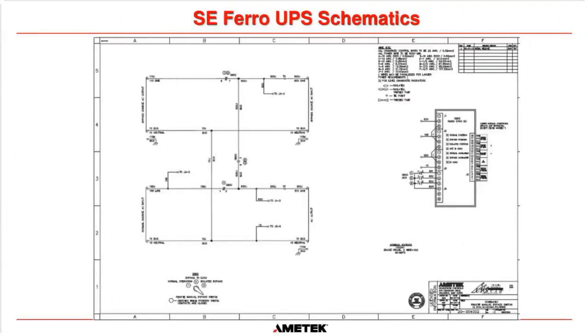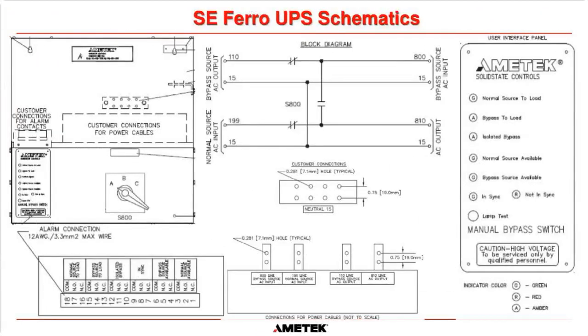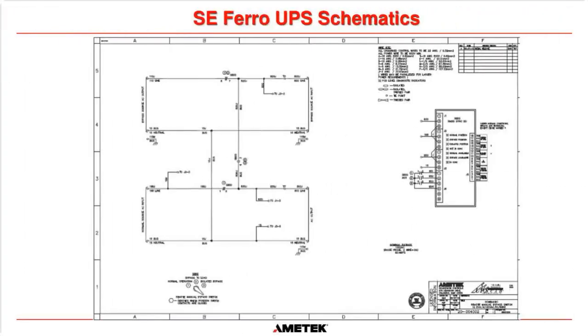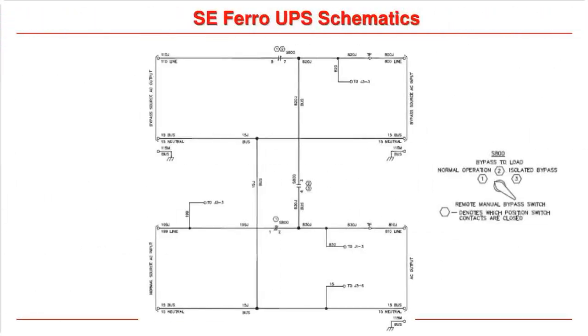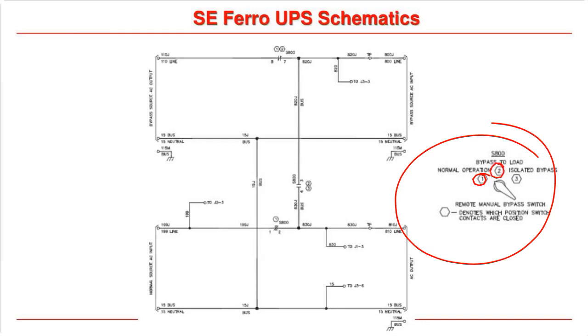Okay. And here is a schematic diagram. It's exactly the same as this one here, but it's just in more detail, and I've blown it up so you can see. Now, here's the rotary switch, and it says normal operation. Any contact with the number 1 written next to it is going to be closed in position 1. Any contact with the number 2 connected to it is going to be closed in position 2, and in position 3, any contact with the number 3 is going to be closed. So let's go through this drawing.